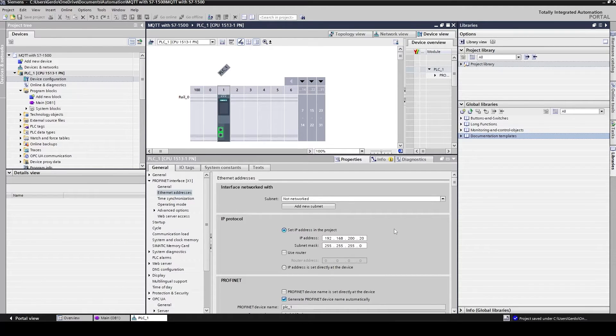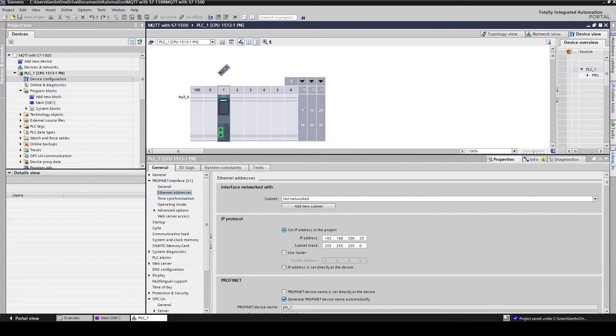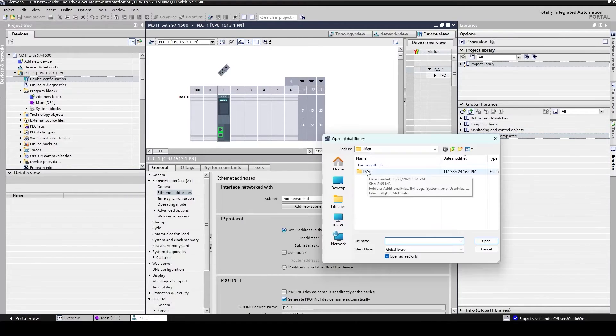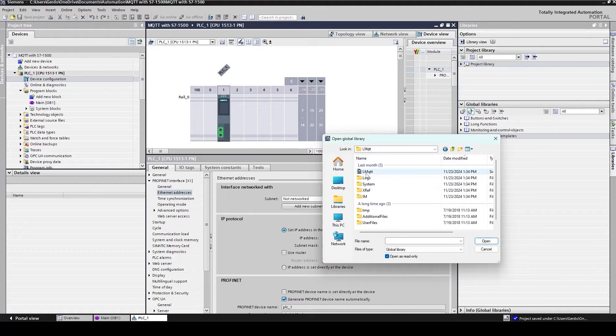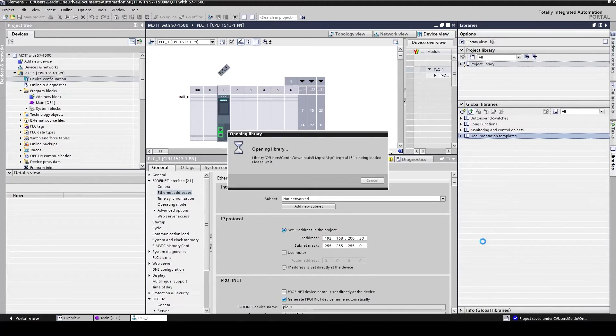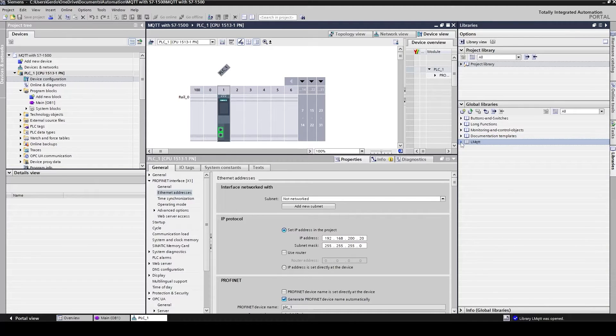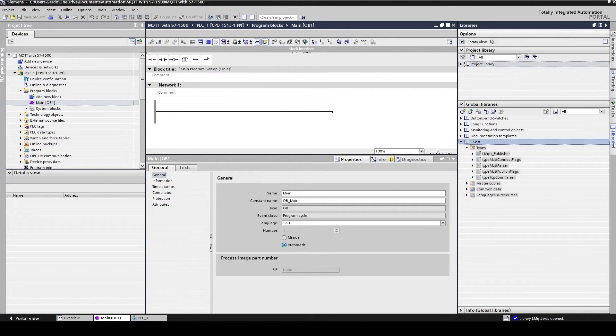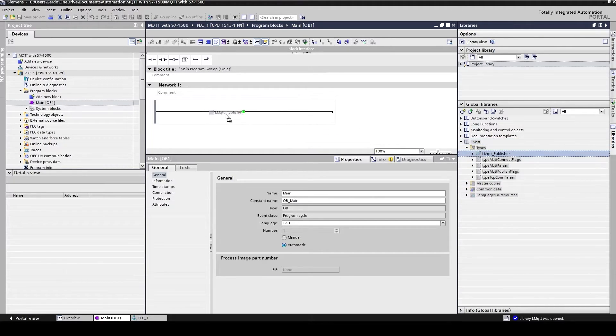I've already downloaded and extracted the zip file. Next I have to import the library into TIA Portal. For that I need to click on the library tab on the right, then click on the green button and point to the LMQTT file and open it up. Then the function block and folders will appear in the global library. Now I open my main OB and from the LMQTT library I drag and drop the LMQTT publisher into OB1.